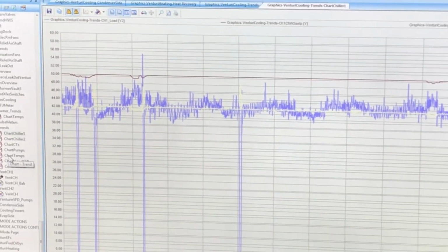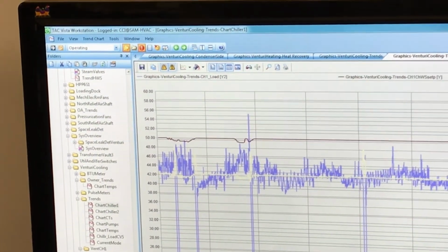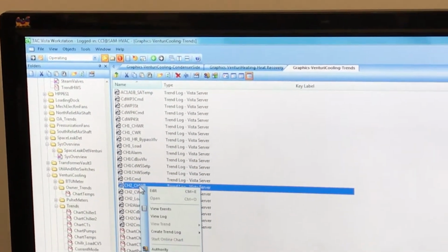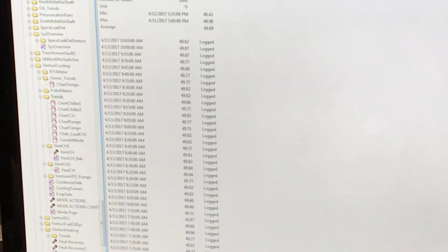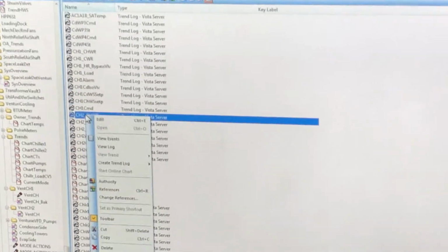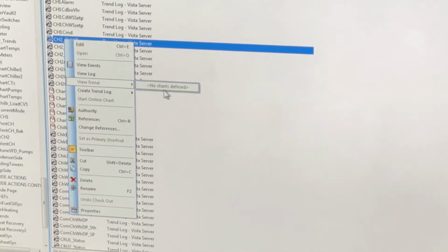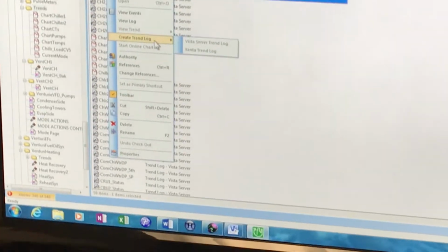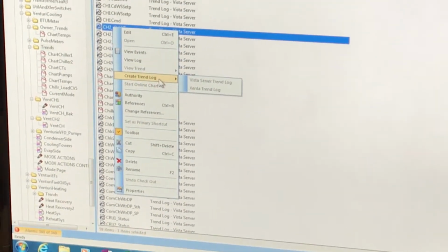There's not a trend chart for each one of those points, so when you go in here, you just click on it and you'll see what it is. If there is a trend chart made for that point, you can right click and go to view trend. But it doesn't have that. So you can create one if you wanted, or create it over here and add that point to it. If you want a class on that, we can do that later. We're not going to add a lot of trends, because that's what bogged down the computer in the first place.